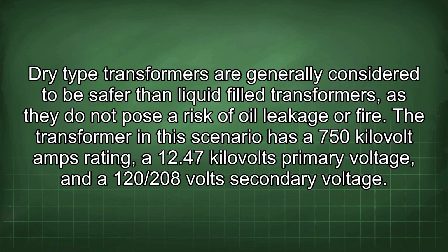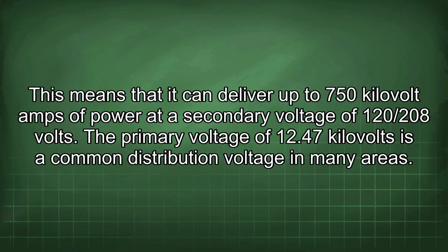a 120/208 volts secondary voltage. This means that it can deliver up to 750 kVA of power at a secondary voltage of 120/208 volts. The primary voltage of 12.47 kV is a common distribution voltage in many areas.